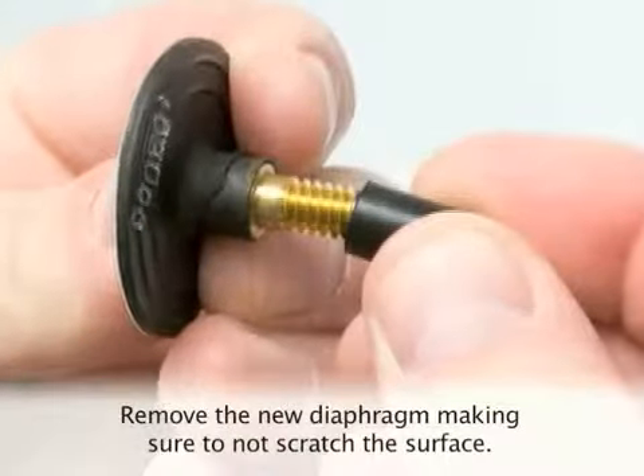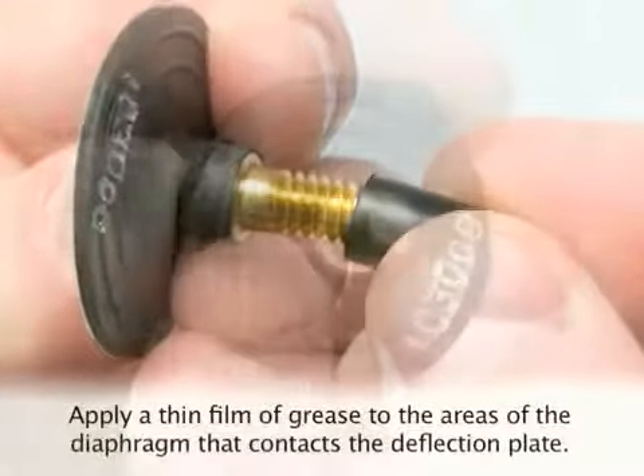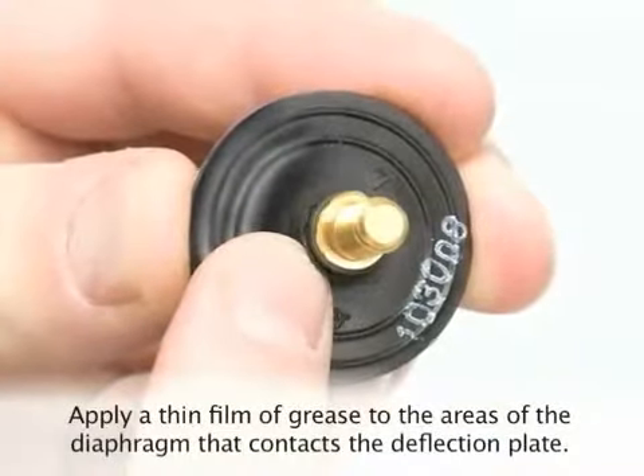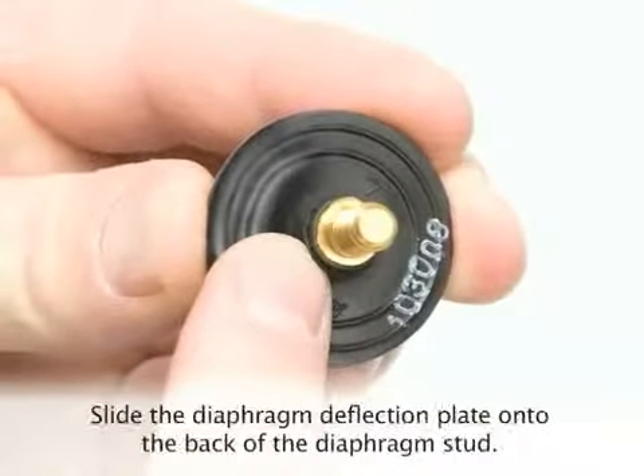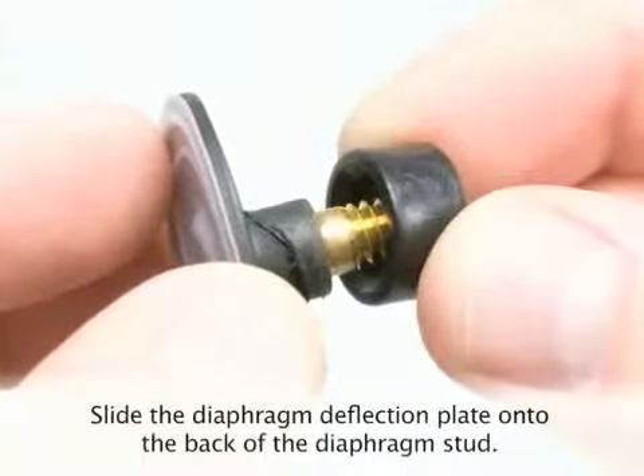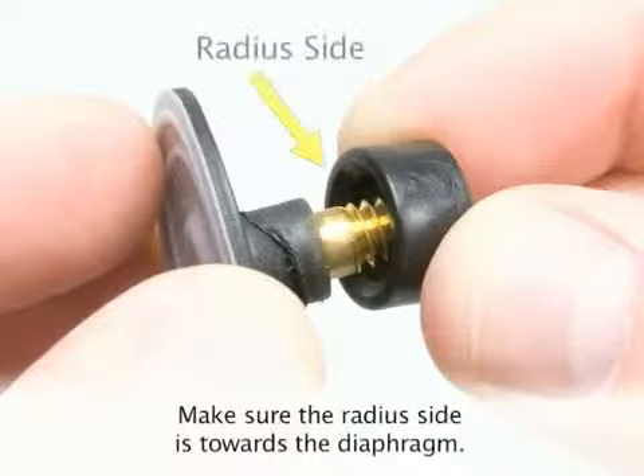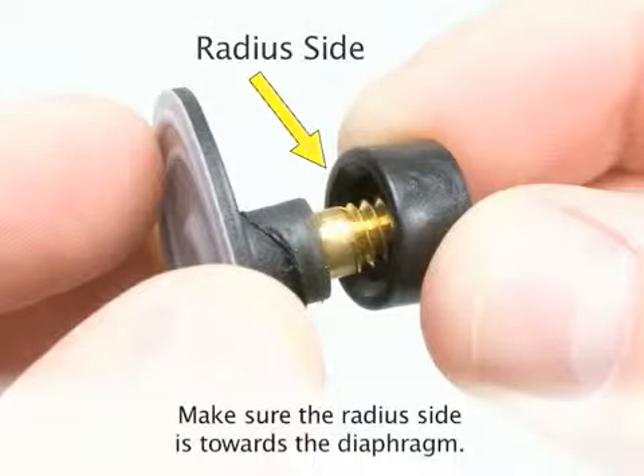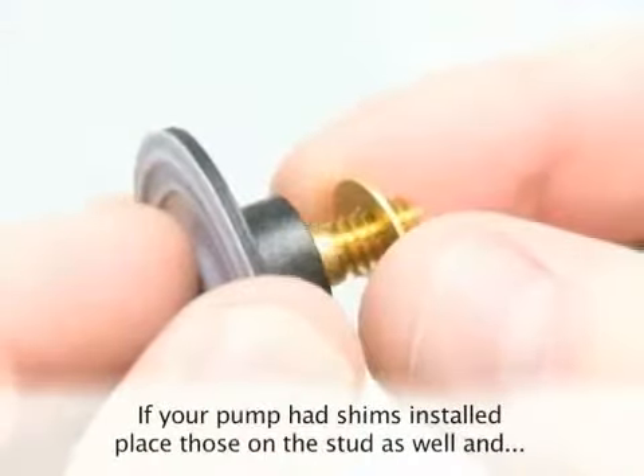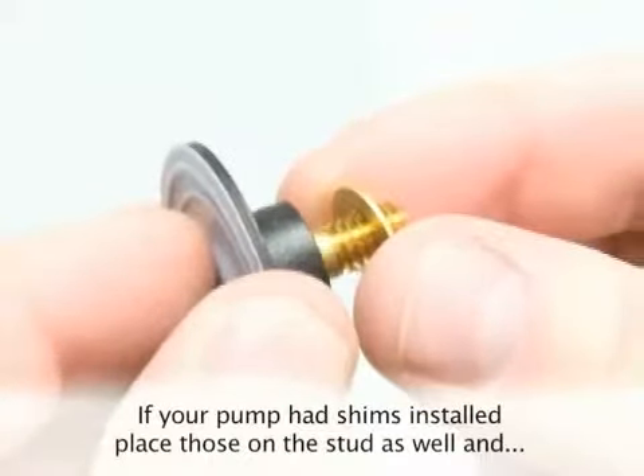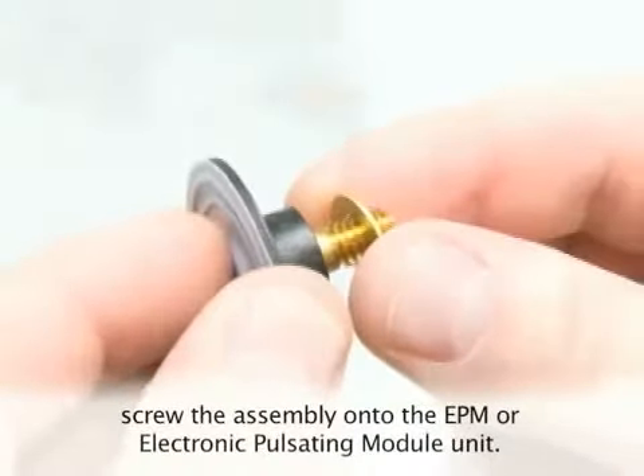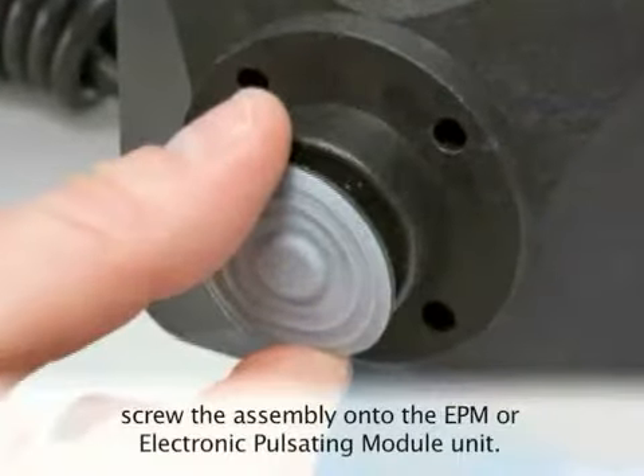Remove the new diaphragm, making sure not to scratch the surface. Apply a thin film of grease to the areas of the diaphragm that contacts the deflection plate. Slide the diaphragm deflection plate onto the back of the diaphragm stud. Make sure that the radius side is towards the diaphragm. If your pump had shims installed, place those on the stud as well, and screw the assembly onto the EPM or electronic pulsating module unit.